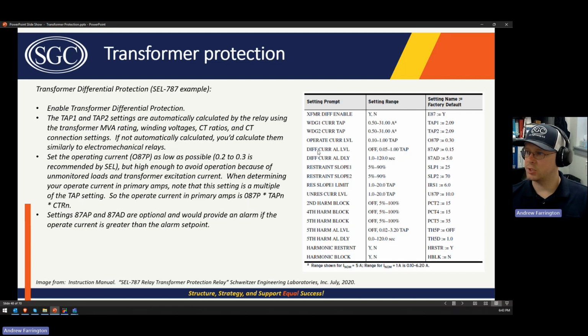Then the next two settings here, the 87AP and 87AD settings, those are optional. This is to basically give you an alarm if you have differential current that is say above negligible, but below the actual operate quantity. So Schweitzer basically says set it less than the operate quantity, typically like half of it.